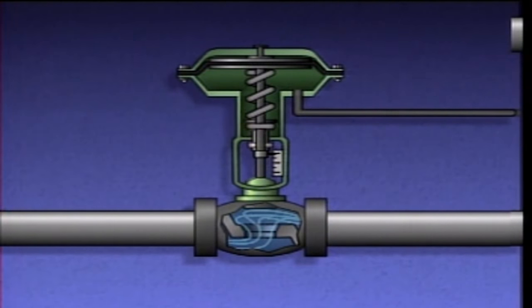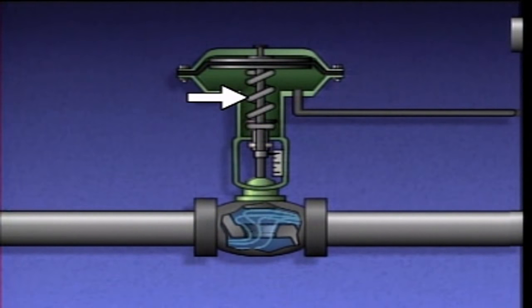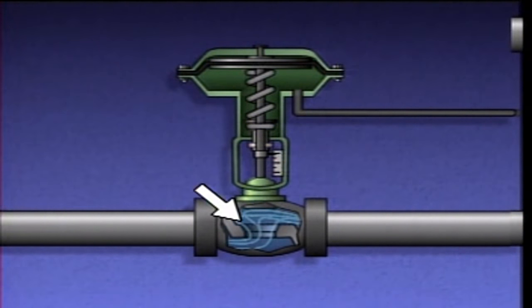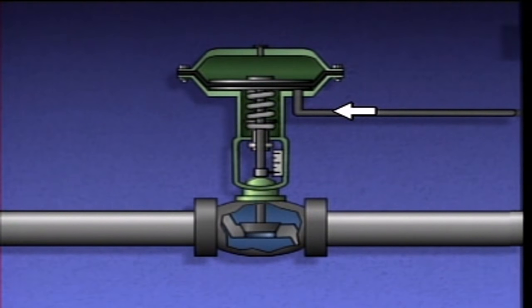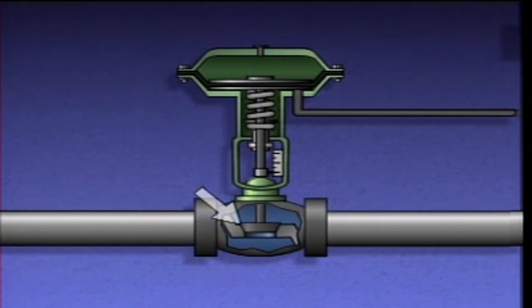This causes the diaphragm to lift, which expands the spring, raises the stem, and opens the valve. When air pressure is reduced, the spring pulls the diaphragm and the stem downward, closing the valve.